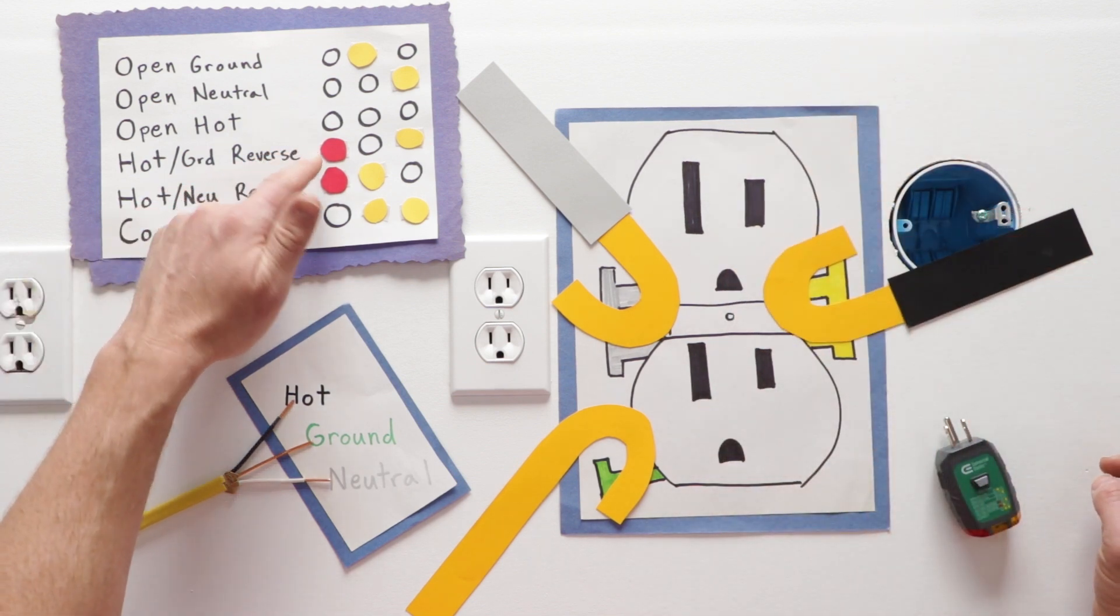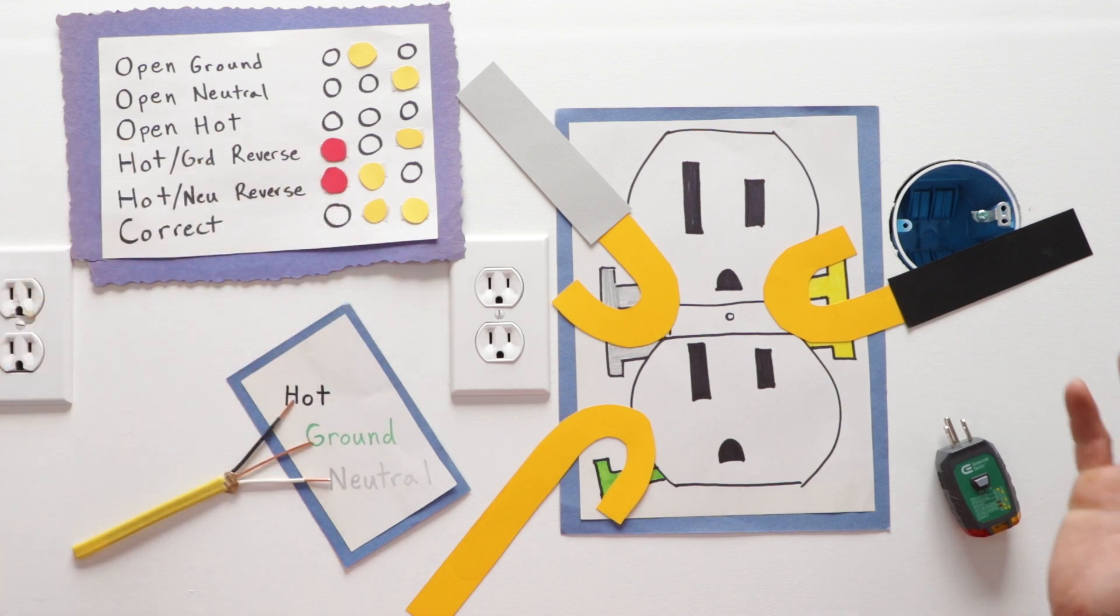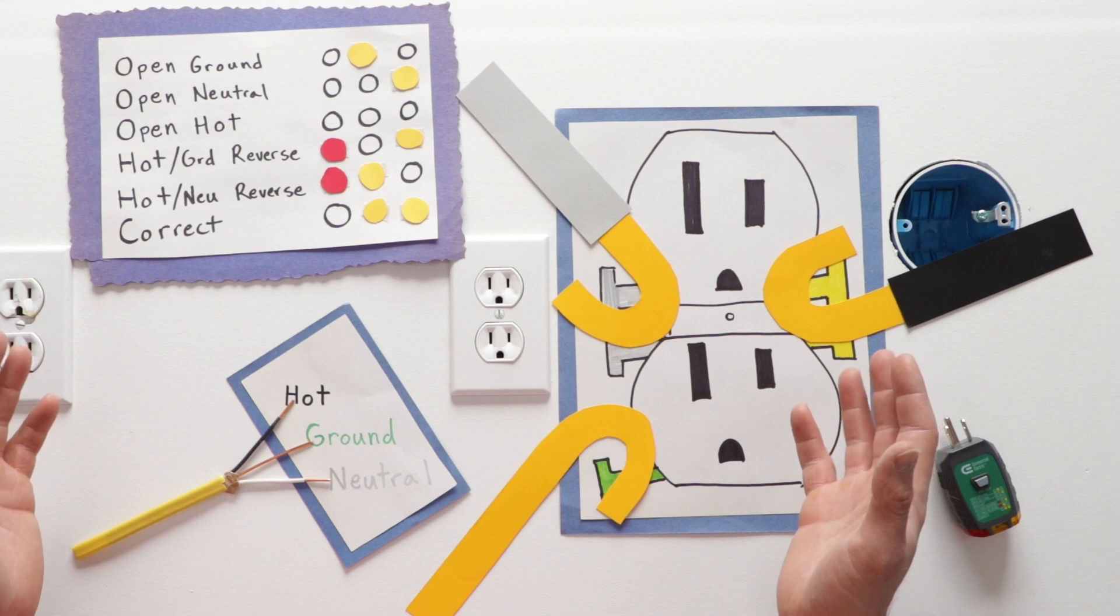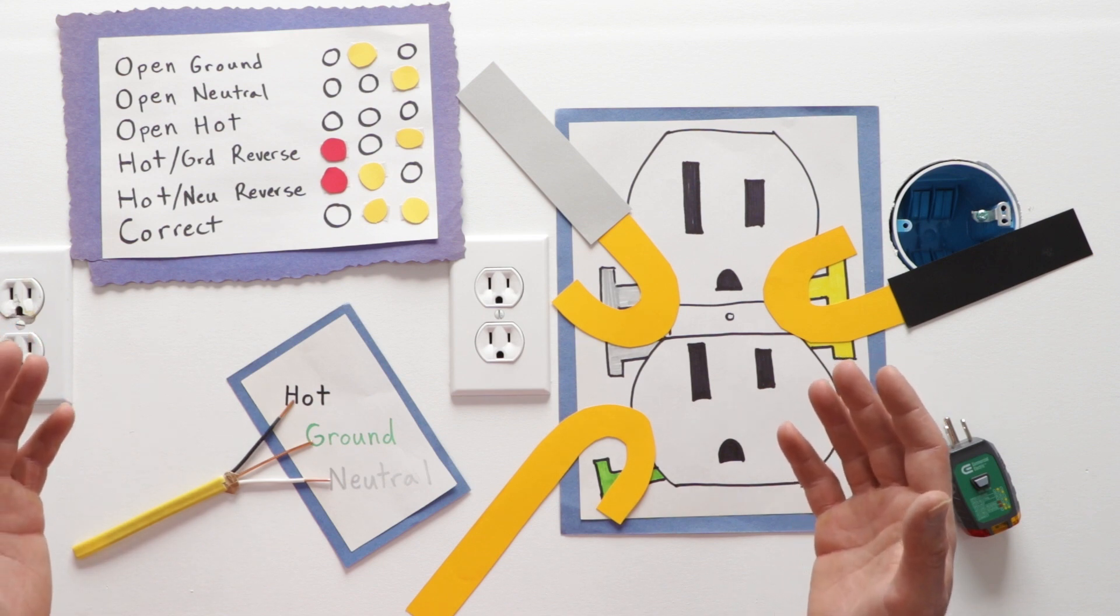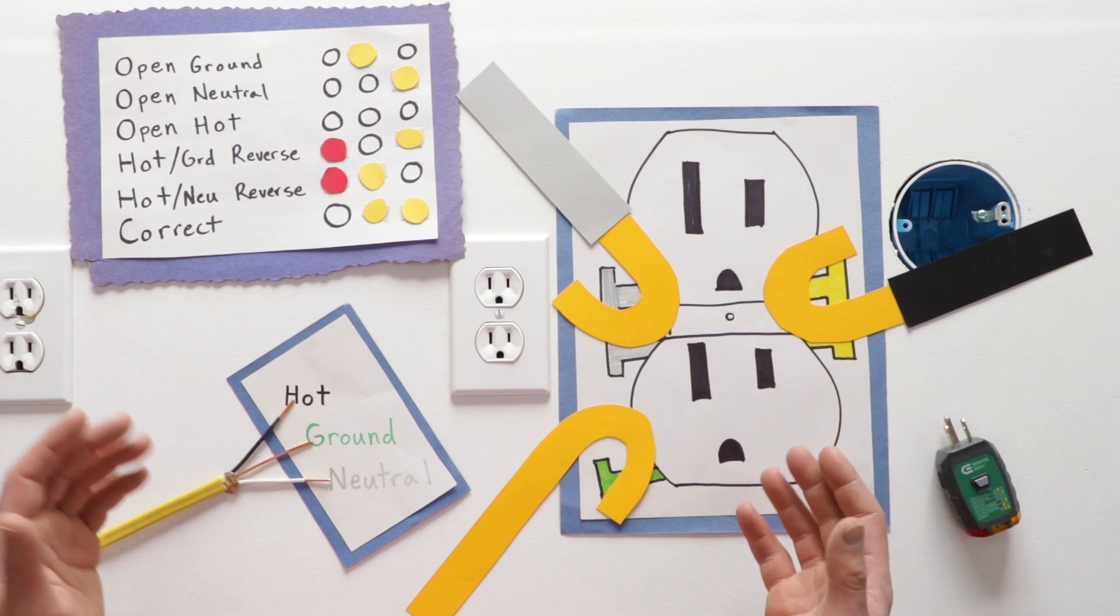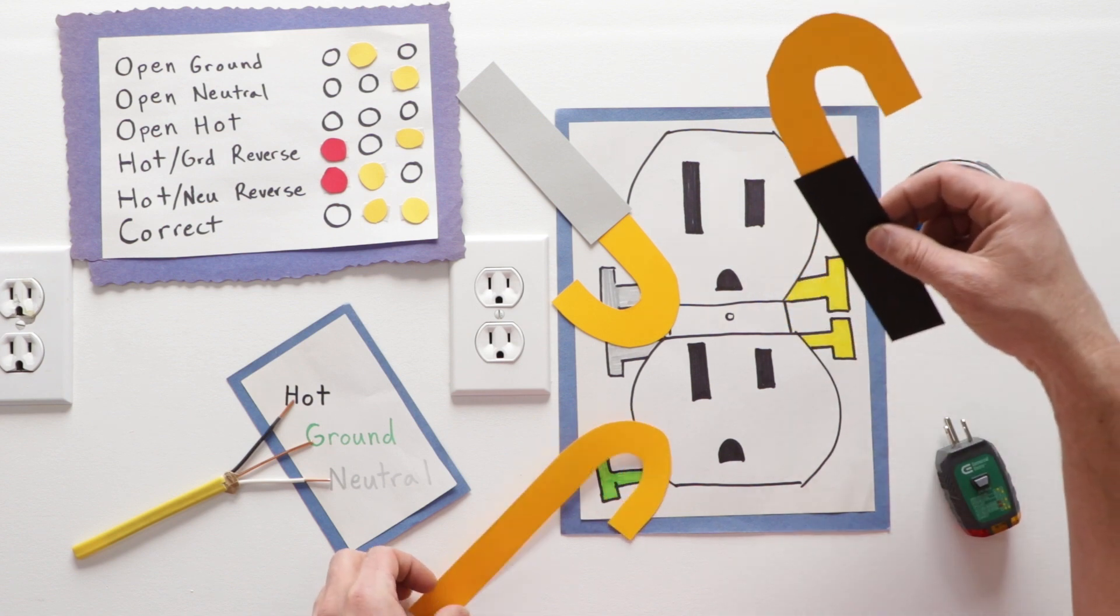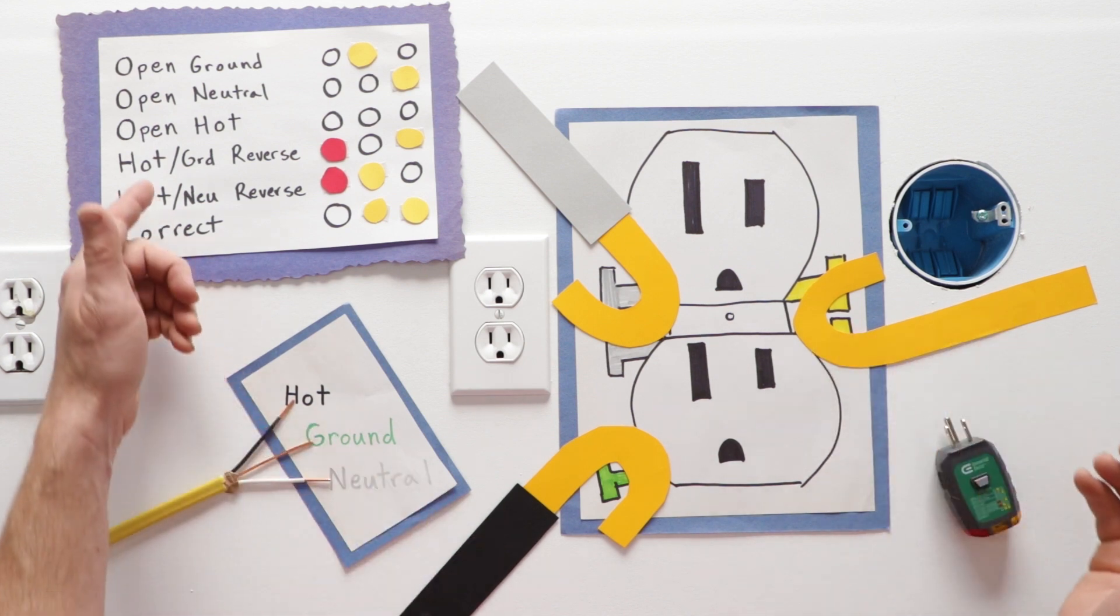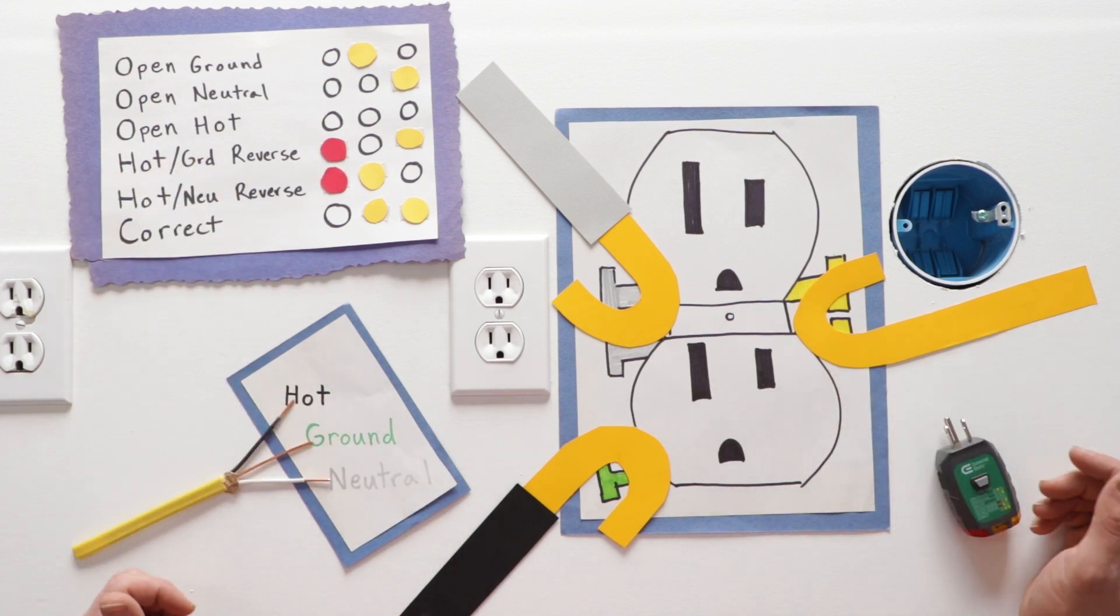The next two arrangements have a red. Red really indicates dangerous. This is a very hazardous situation, especially if you plug in appliances. Say you have your hot and your ground reversed. This is our first situation. This is really bad.